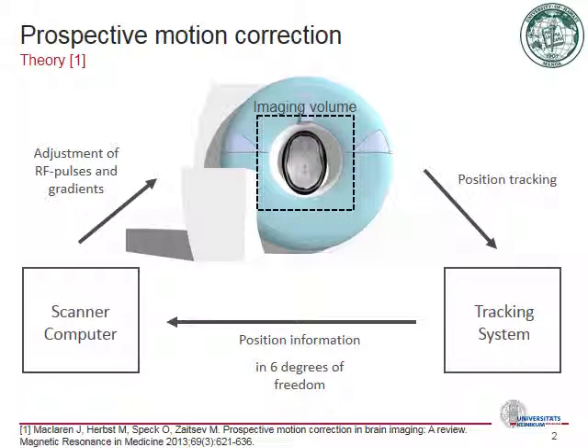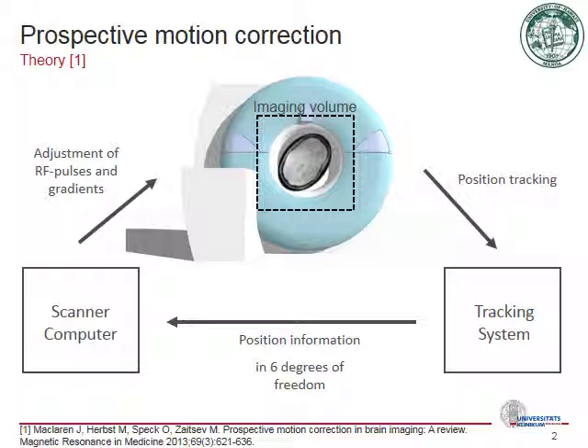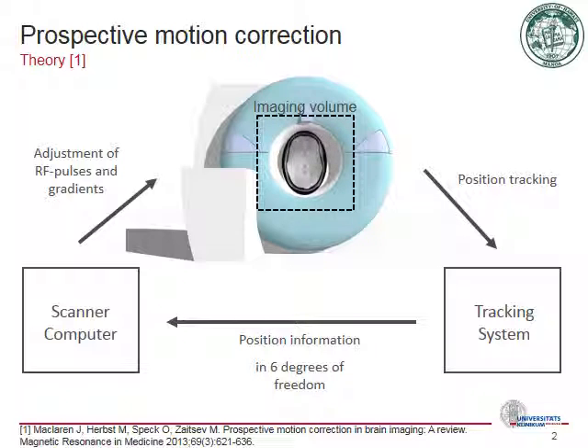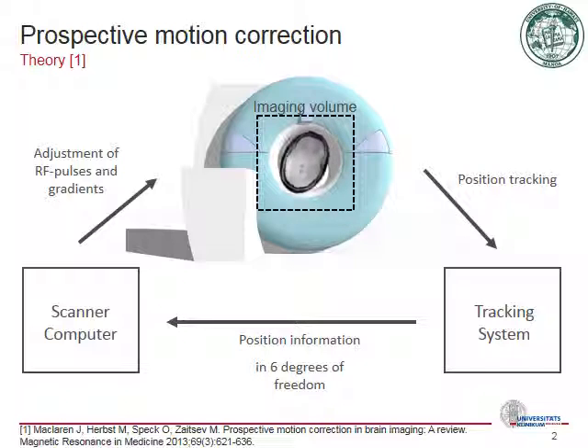Here we see our volunteer in the scanner. Now, let's assume that the volunteer moves during the acquisition. We monitor the movements with our tracking system — a small camera which is placed above the patient in the scanner bore.